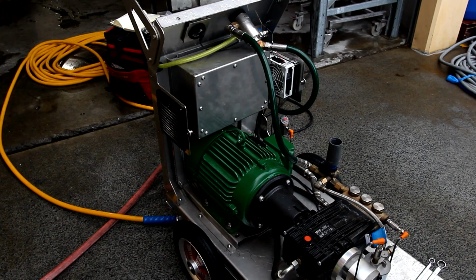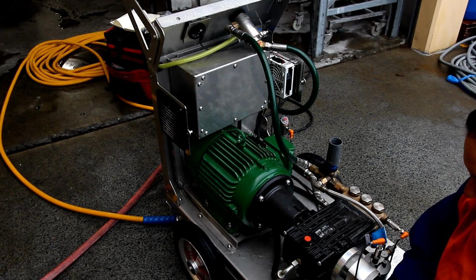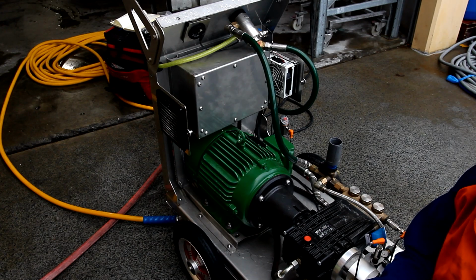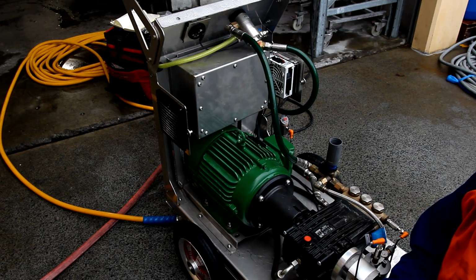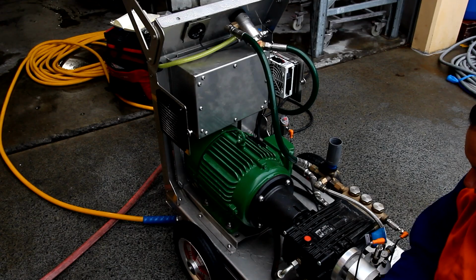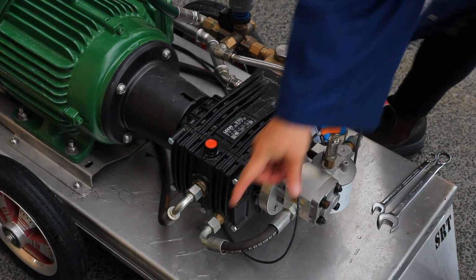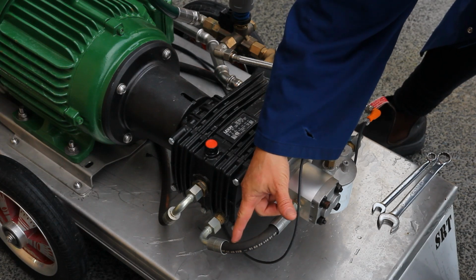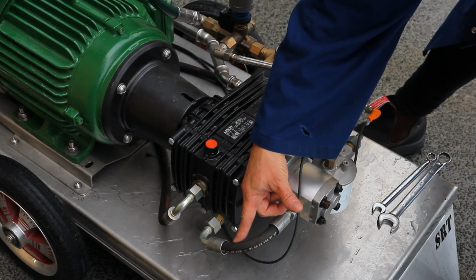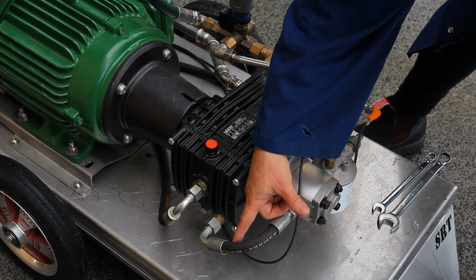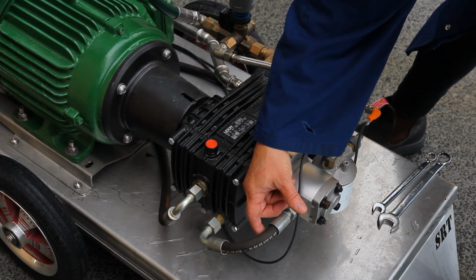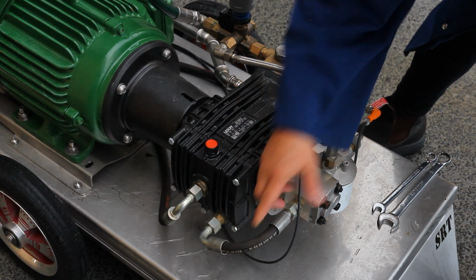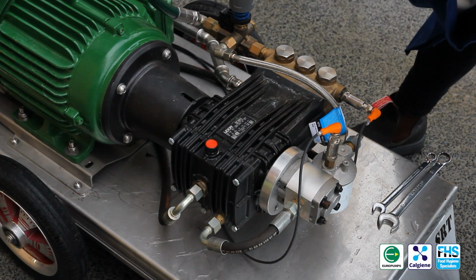The other thing to keep an eye on, because we had an issue with a machine that lost oil pressure. The machine will cut out at 30 kPa, and that's programmed, which is still a generous amount of oil, so you're not going to run out of oil. But we had an issue where this hose collapsed. With hot running, at 80 degrees as a CIP system, this hose degenerated and collapsed, and therefore restricted the oil passing through. So the sensor is doing its job, but there's not enough kPa for the machine to run. We sort of blamed sensors and went around in circles, but it was simply this hose.